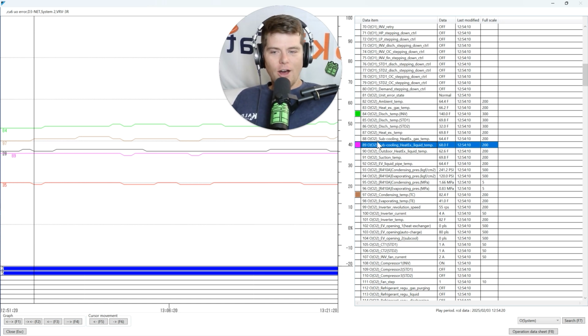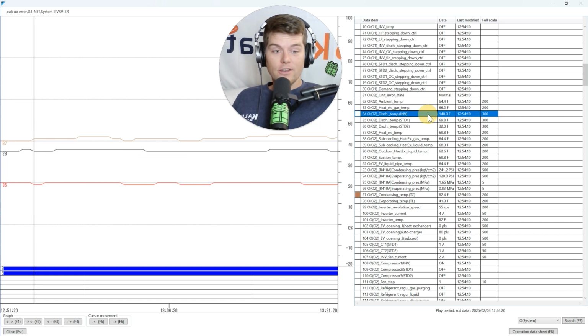So again, if you're out there troubleshooting systems and you're only recording 26 minutes of data, just hang it up and go do something else. The VRF is not for you, right? Go back to working on package units, go back to working on split systems. I get it. R22 is the god of all refrigerants. I'm not going to dispute that with you. However, you've been doing this for 30 years and 26 minutes is all you think you need. And it's not. You're missing it, guys.